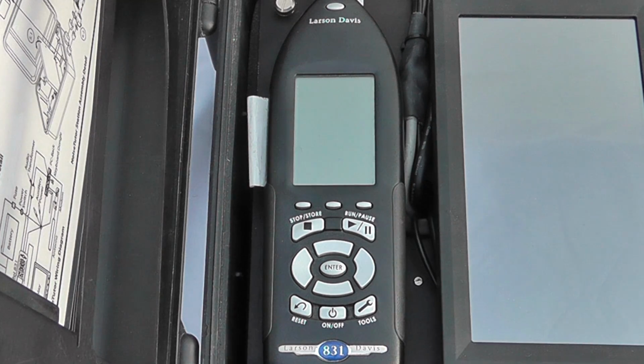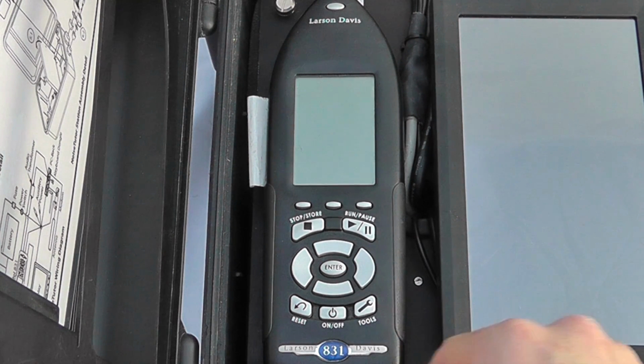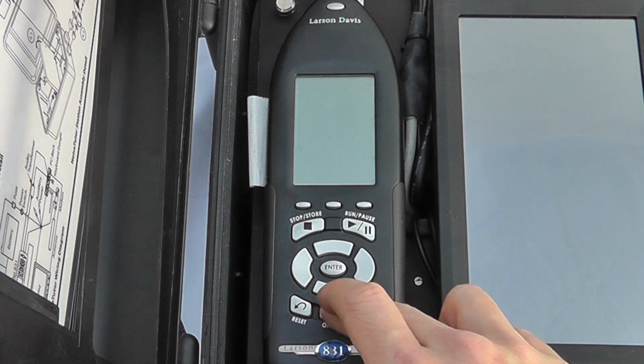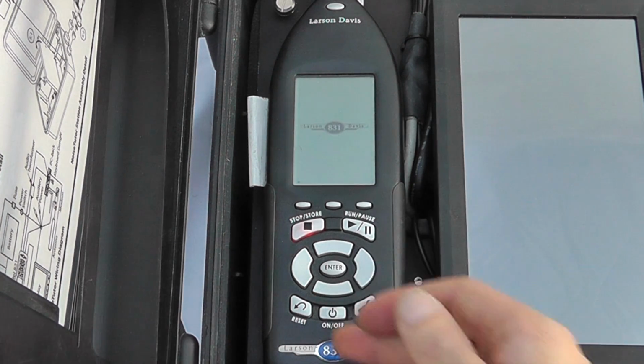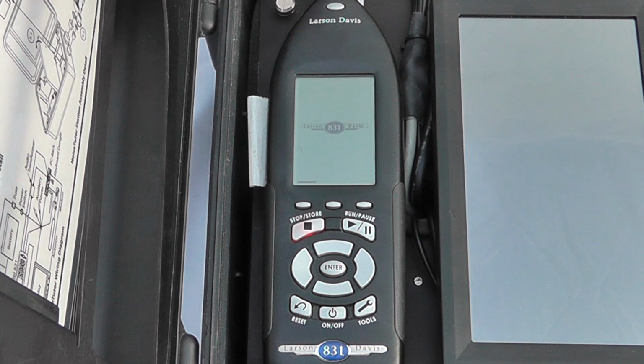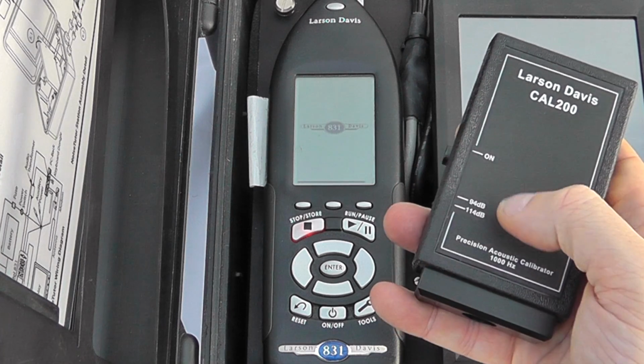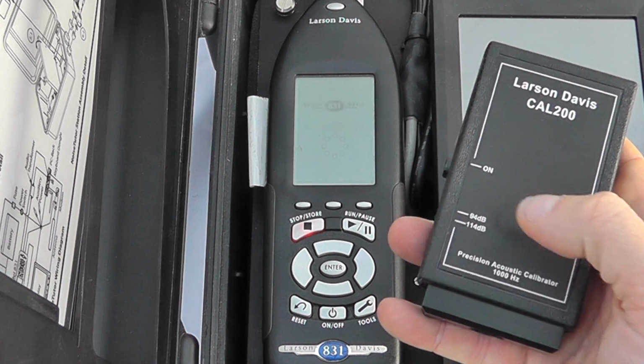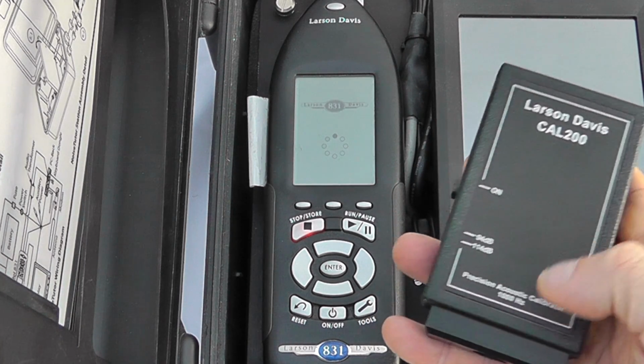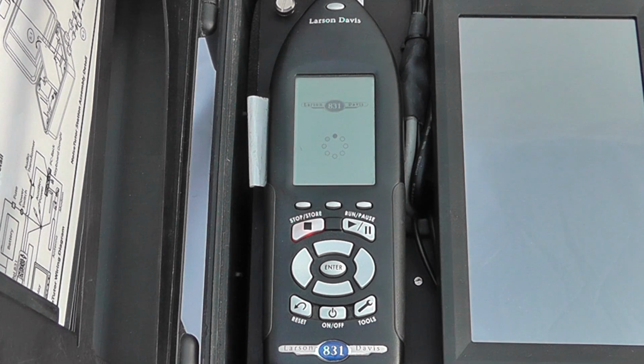So to operate the instrument, again we have battery backup power on here, but this will run from AA batteries or any other system. So to turn the instrument on, we press and hold the on-off switch on the device. I also have a Cal 200 acoustic calibrator. This is capable of calibrating at both 94 and 114 decibels at 1 kilohertz. So I'll use this for the calibration function shortly.